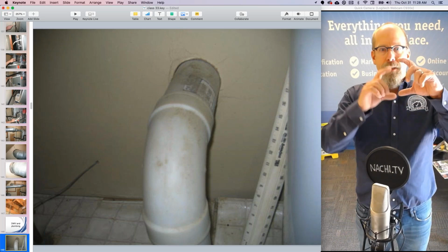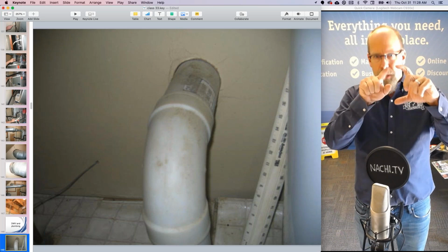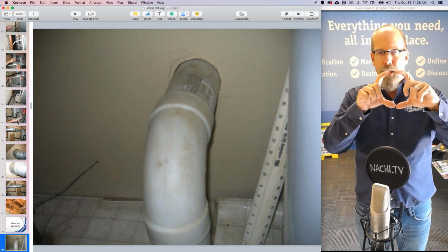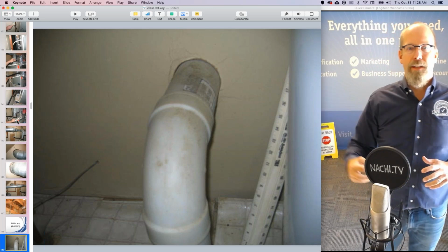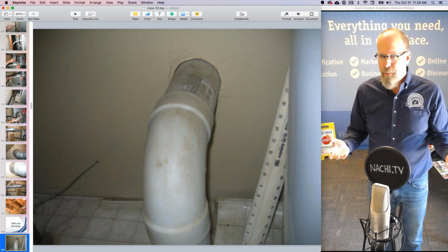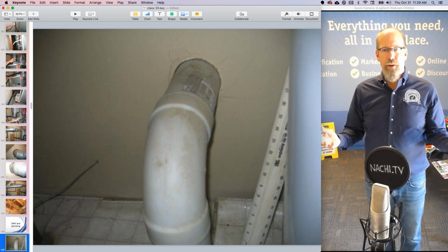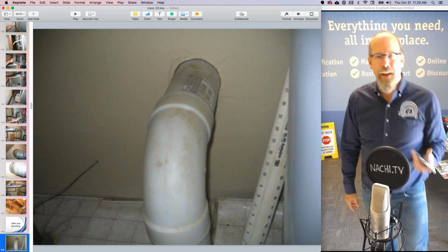There's no sensor like the manometer, you know, with the red or blue liquid in it to show that there's a radon fan sucking the air into the system. There isn't that. And it doesn't look like it's labeled well or properly, or I don't know where this point is. I'm going to pull out my phone, right?